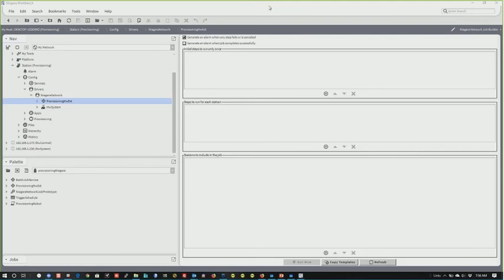So everything else will be intact? Correct. Now, if you have a JACE 8000 and you don't know its passphrase or the platform credentials, there is no way, I'll say presently, to recover from that, other than using the backup button and going into a factory reset, which means your JACE, your station, your modules, everything gets blown away and you're starting from scratch. There is a mechanism that's coded in there. I believe 4.6 is the first place they have it, but they're doing nothing with it right now.